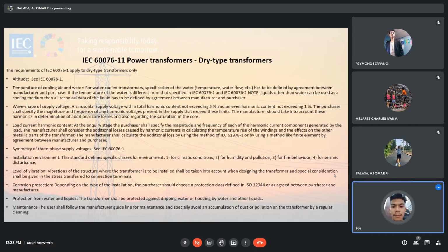The manufacturer should take into account these harmonics in determination of additional core losses and also regarding the saturation of the core. Load current, harmonic content. At the inquiry stage, the purchaser shall specify the magnitude and frequency of each of the harmonic current components generated by the load. And the manufacturer shall consider the additional losses caused by harmonic currents in calculating the temperature rise of the windings and the effects on the other metallic parts of the transformer. The manufacturer shall calculate the additional loss by using the method of IEC 61378 Part 1 or by using a method like finite element by agreement between manufacturer and purchaser.